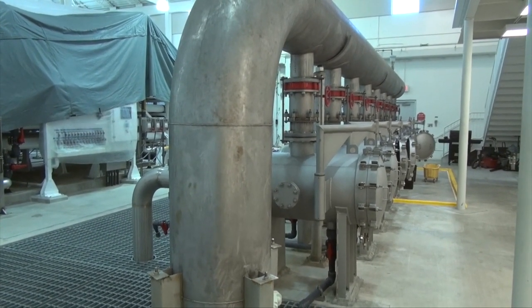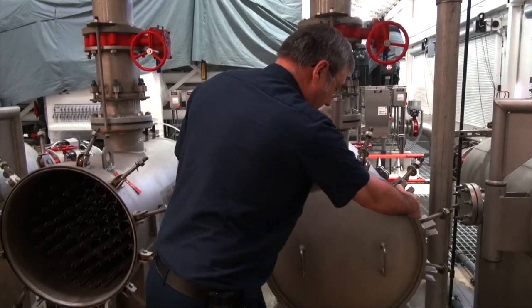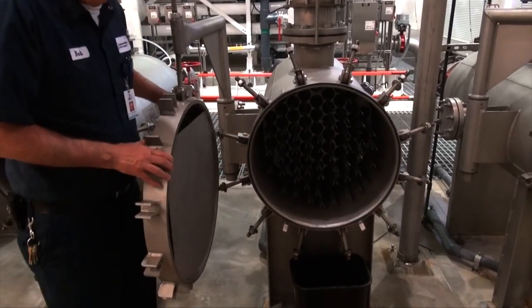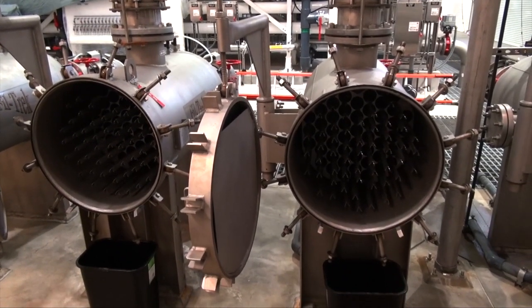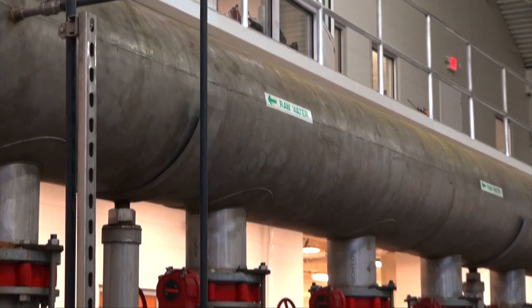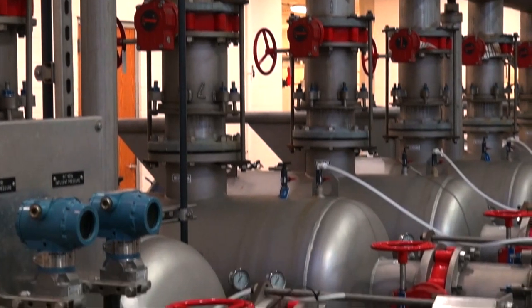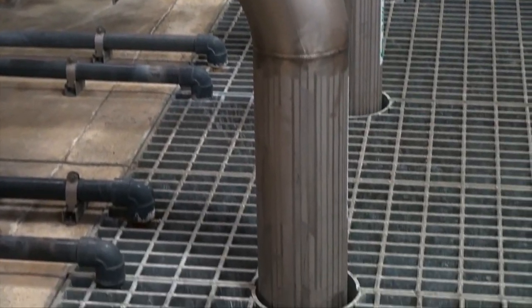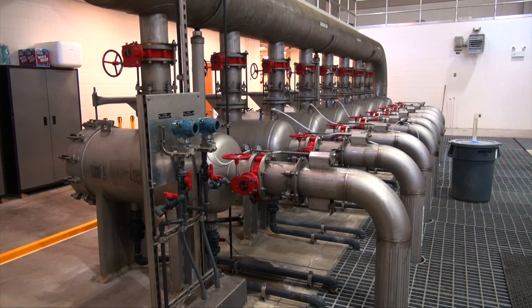The raw water is piped through large filter arrays that remove some of the larger particles. Any sand or dirt that may have traveled with the water from the well are removed here. At this stage of the treatment process, anything 5 microns or larger is filtered out of the water. These filters are tested daily and changed every 6 months.